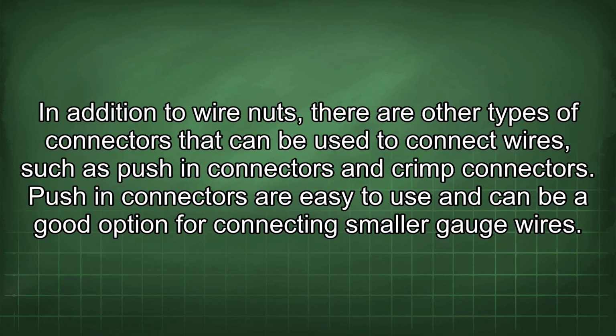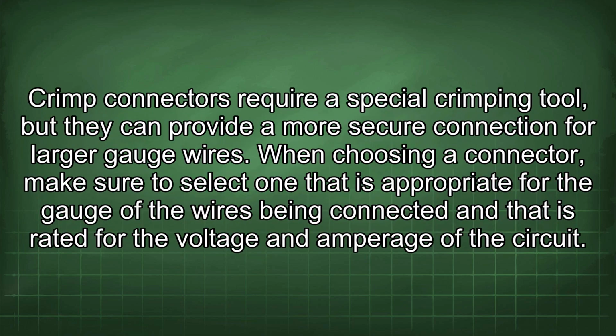In addition to wire nuts, there are other types of connectors that can be used to connect wires, such as push-in connectors and crimp connectors. Push-in connectors are easy to use and can be a good option for connecting smaller gauge wires. Crimp connectors require a special crimping tool, but they can provide a more secure connection for larger gauge wires. When choosing a connector, make sure to select one that is appropriate for the gauge of the wires being connected and that is rated for the voltage and amperage of the circuit.